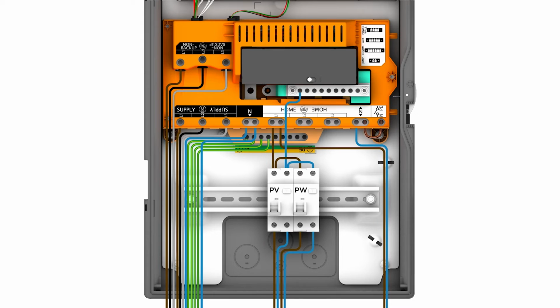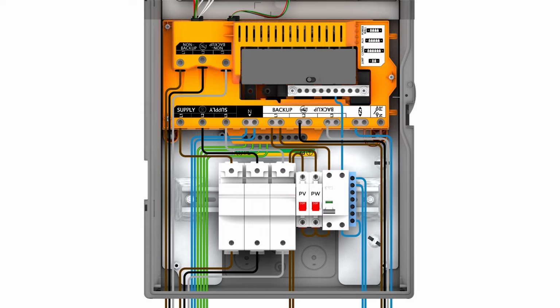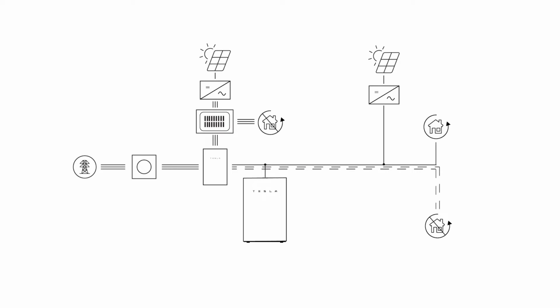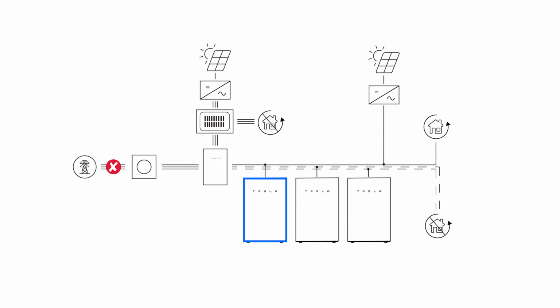Single-phase loads are connected to Line 1 at the home label as seen earlier. Additionally, single-phase loads can also be connected to Lines 2 and 3, however, only one phase is backed up. In this example, Line 1 has been selected as the backed up phase. Powerwall can be installed on either one phase or all three phases. In this scenario, all three phases will operate in self-consumption mode. However, only one phase will be backed up during a grid outage. The other two Powerwalls will shut off. The phase to be backed up is selected by the installer during the commissioning process.